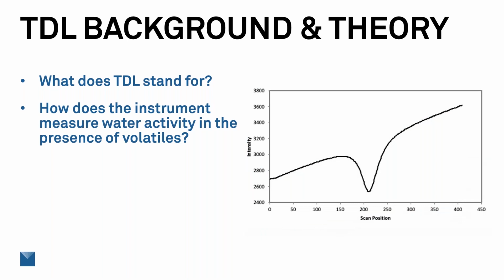To the first point, again, I mentioned it briefly, but dew point based sensors, when a volatile, and to define a volatile, it's a compound that will go into the headspace of the chamber and co-condense on the mirror. So a good example of that is ethanol. So if you have concentrations of ethanol, then they will change the perceived and measured water activity when using a dew point sensor. So this graph here is showing the absorbance peak of water from the tunable diode laser.